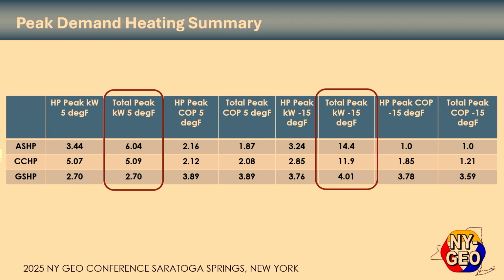So let's take a look at the actual heat pump. So here's the heat pump, and you can see the cold climate heat pump versus the air source. Now, is it immediately obvious to you guys why the cold climate heat pump is 5 and the air source 3.44? Anybody want to guess? Well, you've got a bigger compressor that's running at a higher speed to give you more capacity, right? So it's over-revving, so to speak, comparatively to the air source heat pump. So that's why you see those two diverge here, where on the cooling side you didn't see it.